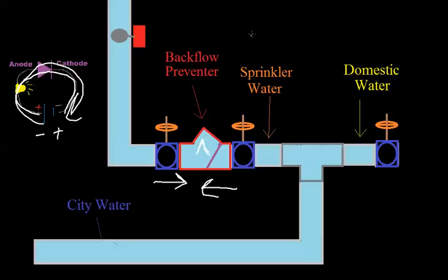No water's flowing. That water's just sitting there. But if one of those heads burst and water started to flow, you need to know that as well. And they have a device that's called a water flow switch, which is just basically a paddle like this. This is my water flow switch right here on the left. And there's a little box where your electrical connections are hooked up, where it's hooked up to the fire alarm panel.